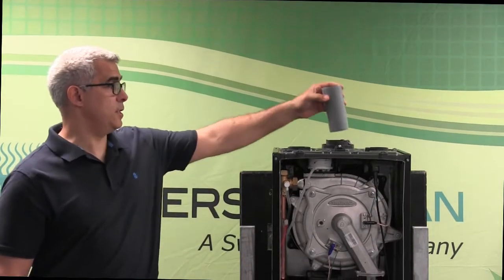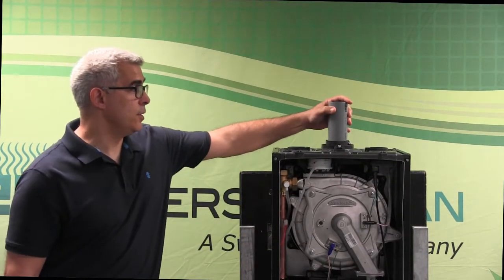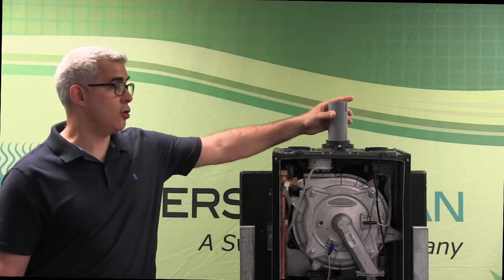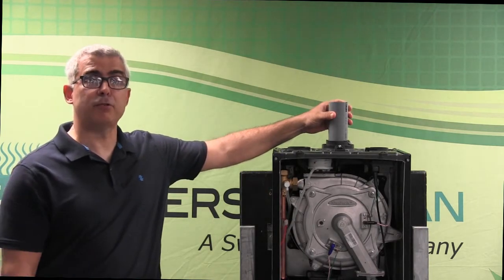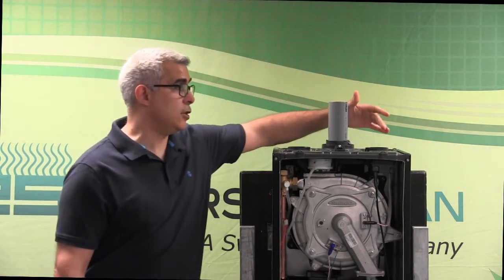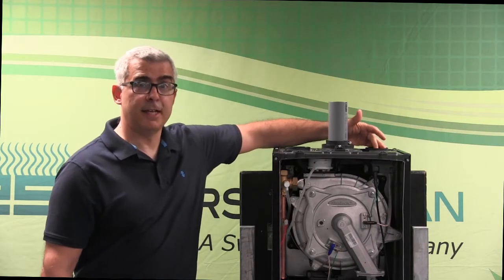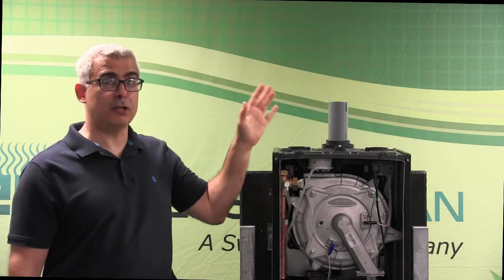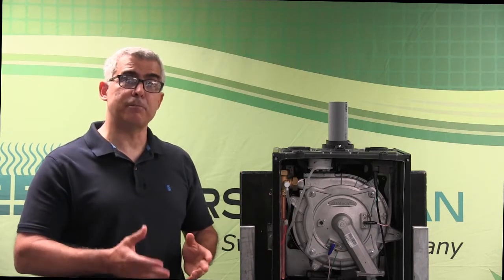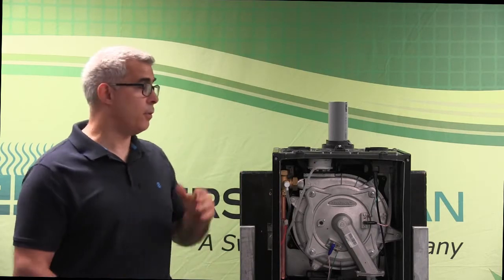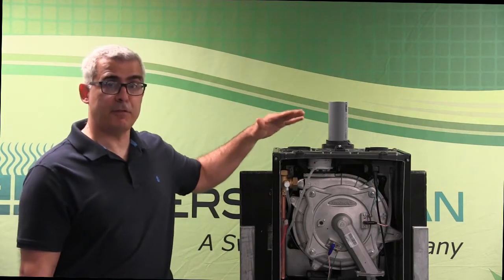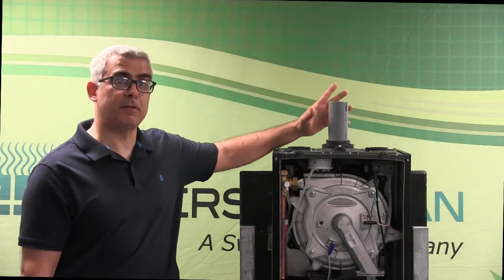Number 2, vent runs. There's a 2-inch piece, CPVC piece that comes with the boiler. You put that on the exhaust. The exhaust can run, if you run 2-inch, up to 100 feet. The intake could either go on the left or the right side. That could be 2-inch. That could go 100 feet. That's a total of 200 feet of 2-inch. Now you can upsize it to 3-inch. And if you go with 3-inch, you can go 150 feet on the intake and 150 feet on the exhaust.